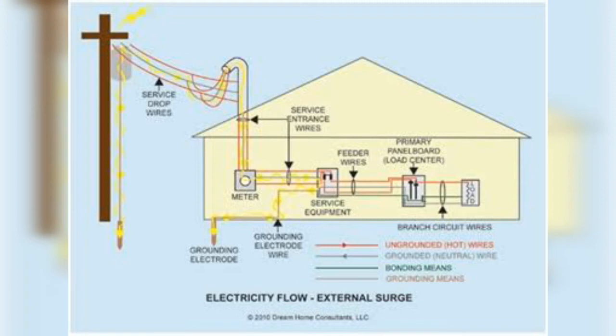How does grounding solve the problem? Grounding provides a bypass, shunt or shortcut through which electricity can flow instead of passing the current through the person who touches the appliance's wires. It is called the equipment grounding conductor, EGC. It returns from the electrical panel through the fixed wiring to all socket outlets and fixed appliances such as the range, water heater, lights, switches and ceiling fans in their homes.